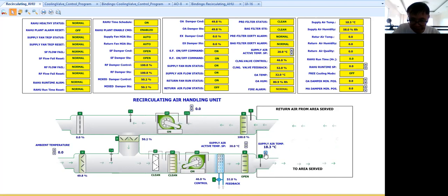Now let's see, there will be a little rise, okay? Now you will notice here that the valve will try to, okay, again, it's still closing because there is still a negative error here. Okay, let's see. Now it's 20.3. See, it opens a little. Okay. Now, if it is 21, then it will close a little more. Right? Okay, so perfect. Beautiful. Okay, if you are the BMS engineer, if you are seeing this kind of response, then you should be happy.